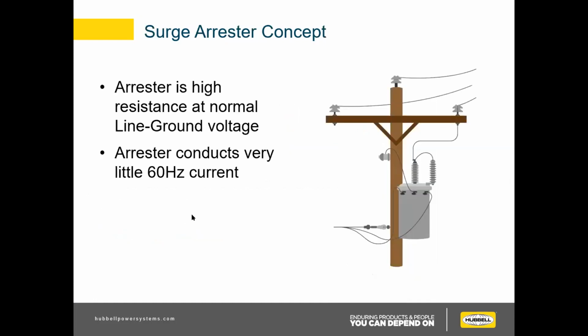So concept, like I said earlier, it's a high resistance at line to ground voltage. So it just sits there day in and day out, doing the same thing, pretty much nothing. So at the line to ground voltage, the arrestor conducts very little 60 hertz current, like in the milliamps, very, very small amounts.